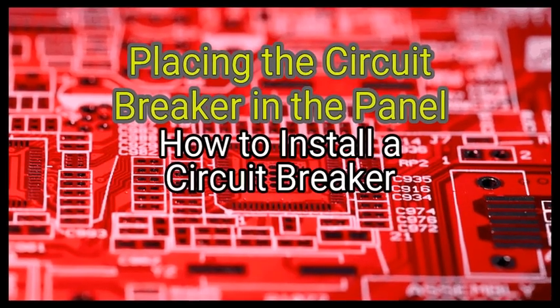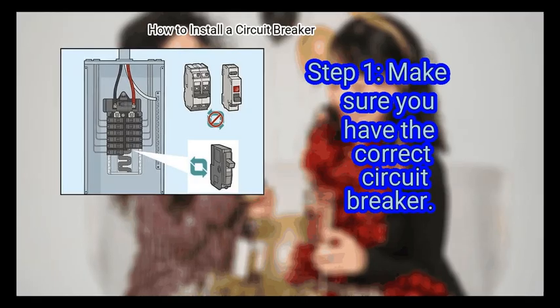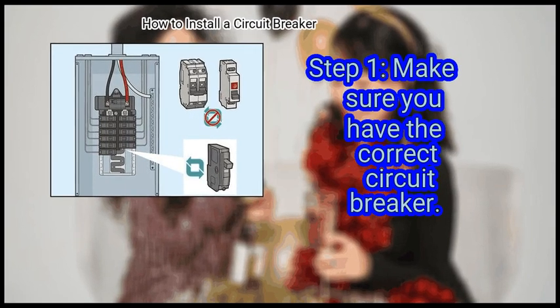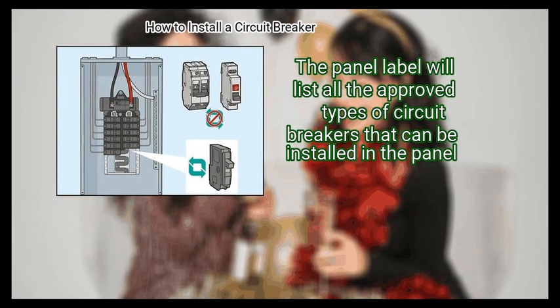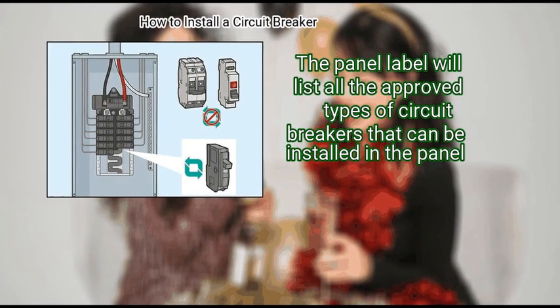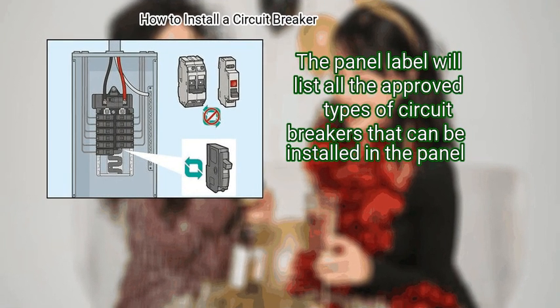Method 2. Placing the circuit breaker in the panel. First, make sure you have the correct circuit breaker. The panel label will list all the approved types of circuit breakers that can be installed in the panel.